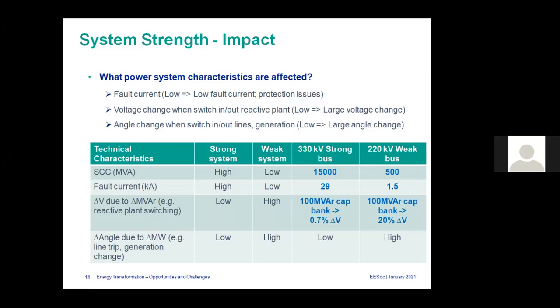When you come near the high fault level locations or stronger system locations, you see larger reactive plant. Even in Sri Lanka, if you go and check near the Western Province, the capacitor sizes may be larger compared to far away. If you look at Anuradhapura, Jaffna, or Hambantota, the capacitor sizes should be smaller. It's because the voltage change you expect is much less at a stronger location. It's the same in Australia. If you have a 330 kV system, you sometimes have 200 MVA capacitor banks, but in the 220 kV network we have only 10 MVA or 20 MVA capacitors. It's because of the voltage change you see when you switch in the reactive plant.